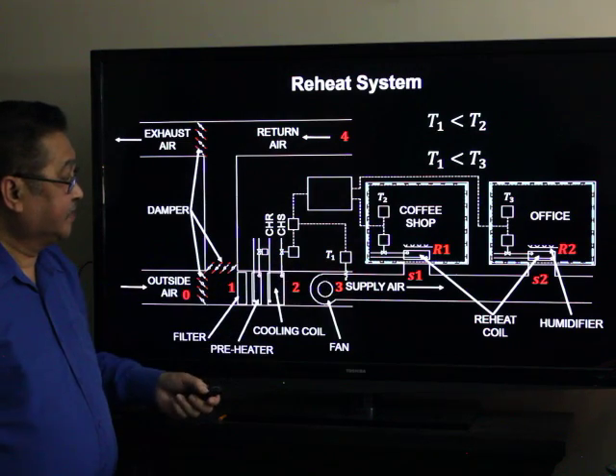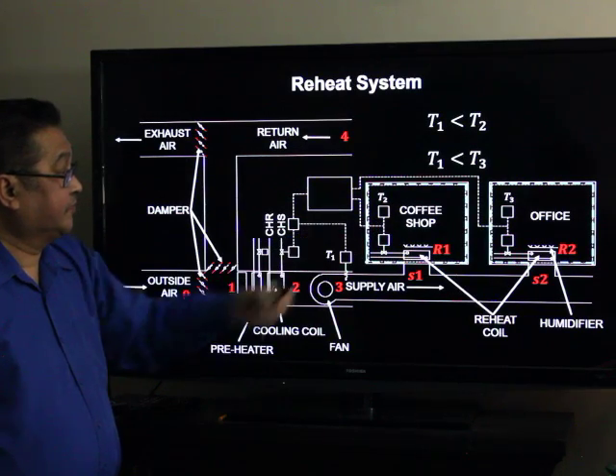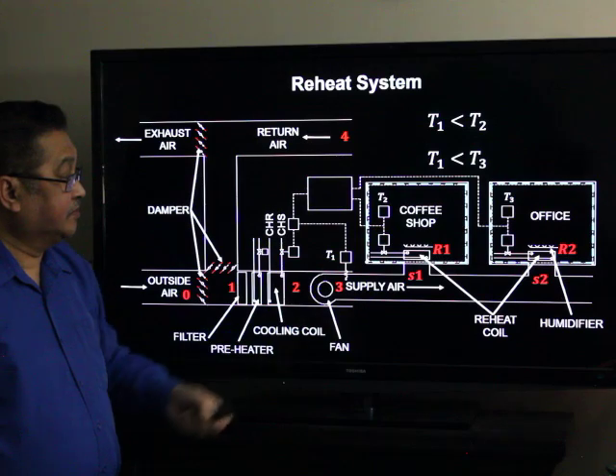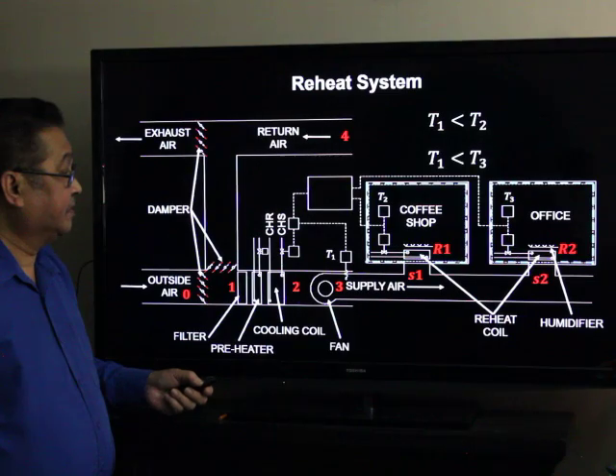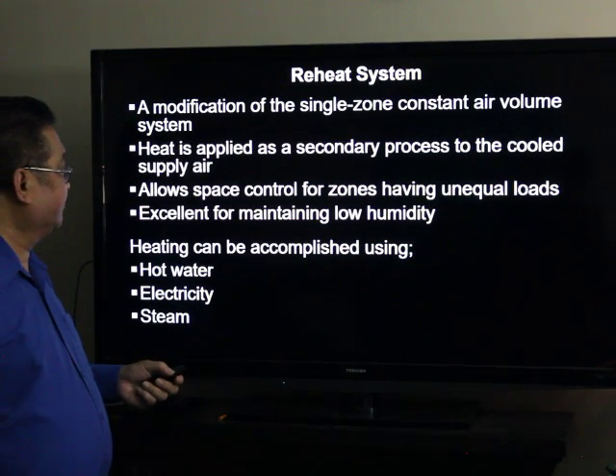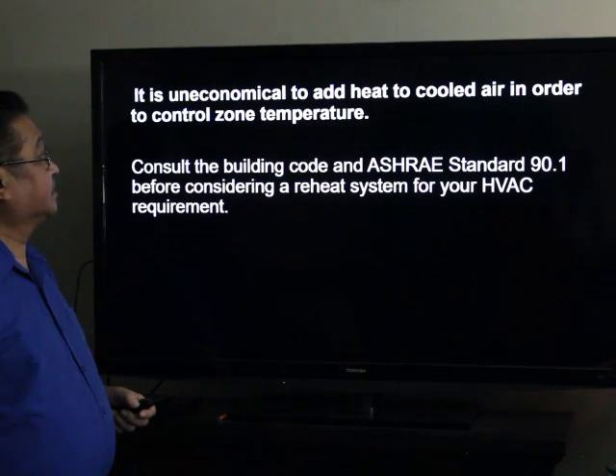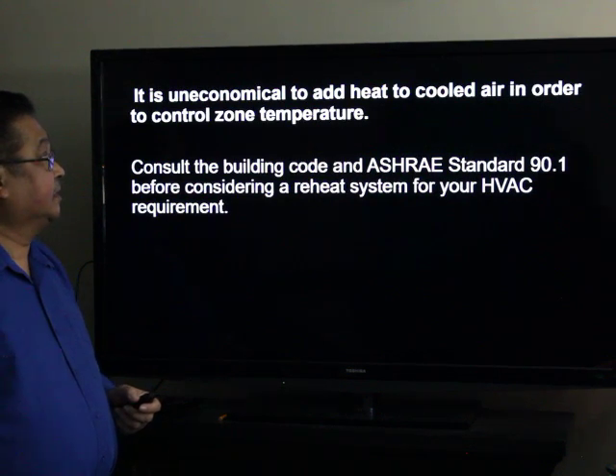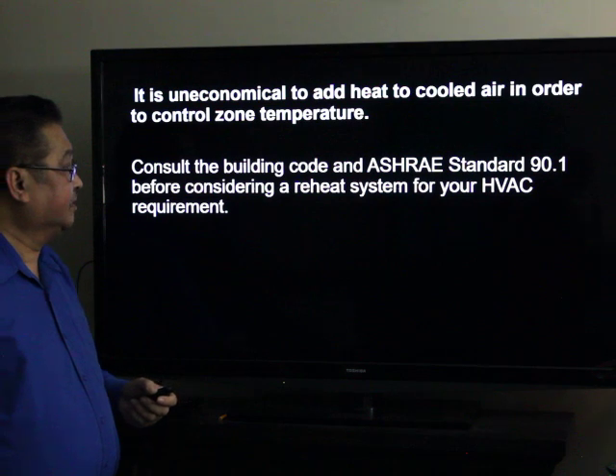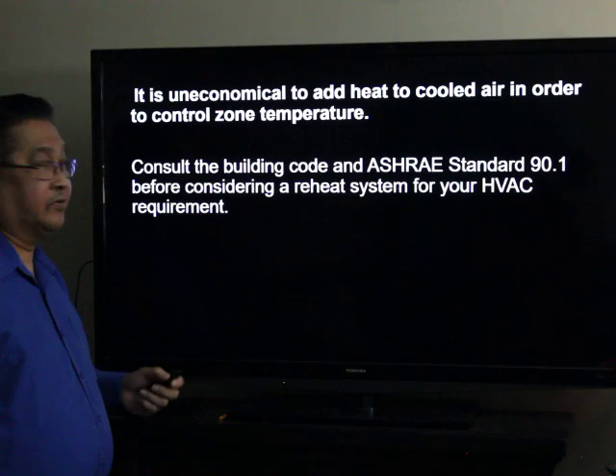With the reheat system, you have a reheater for each zone. In cases where the supply air temperature is lower than the temperature set point for both the coffee shop and the office — T1 is less than T2 and T1 is also less than T3 — you can use the reheat coil to raise the temperature when it is too cold. Heat is applied as a secondary process, and the heating can be accomplished using hot water, electricity, or steam. It is uneconomical to add heat to cold air in order to control zone temperature. You should consult the building code and ASHRAE Standard 90.1 when considering a reheat system for your HVAC requirement.